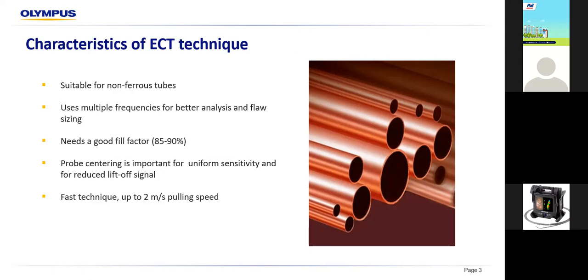Do make sure that we conform with this recommendation, because if you don't have a good fill factor, the amplitude of defects will become lower, and at the same time you will have a lot of false indications. I mean, you will not be able to size the correct defect flaw. And then, of course, it's a fast technique, so you can have up to 2 meters per second pulling speed when using this ECT technique.